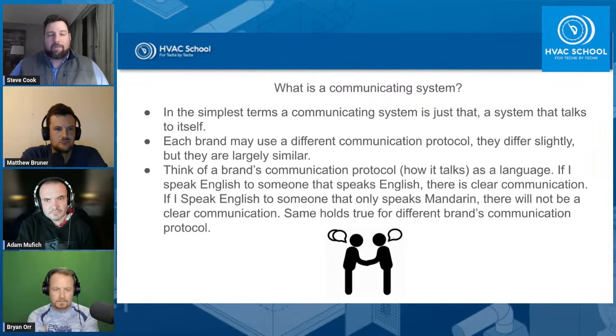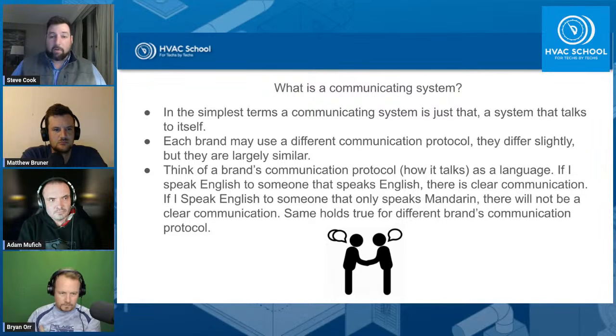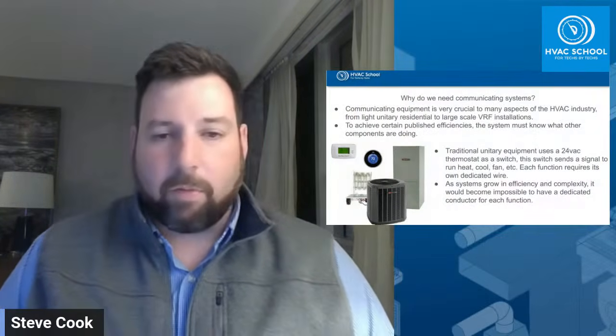Now, if you think of a communicating system, there's a lot more going on. In order to get the efficiencies, we might have inverter-driven equipment. So for a compressor to speed up or slow down, it needs to see what the thermistors are doing, what the compressor is doing, the temperatures throughout the system. For that to happen, there has to be communication between the two in order for it to speed up or slow down.